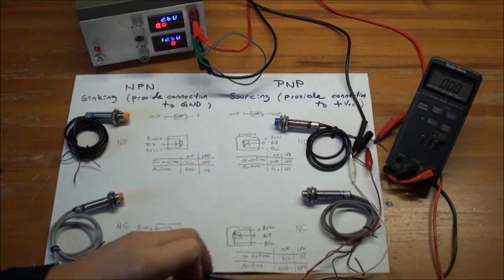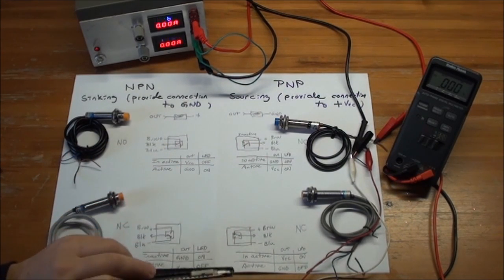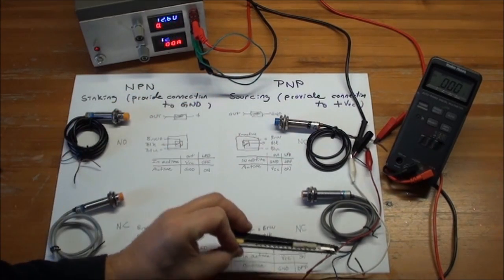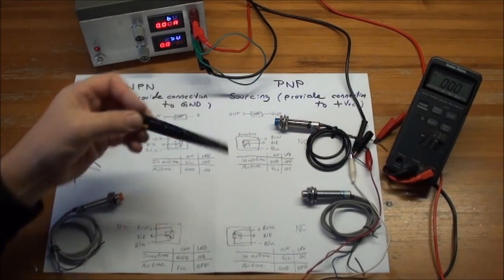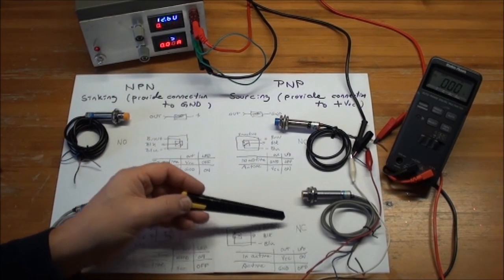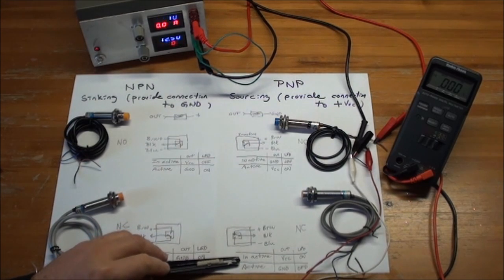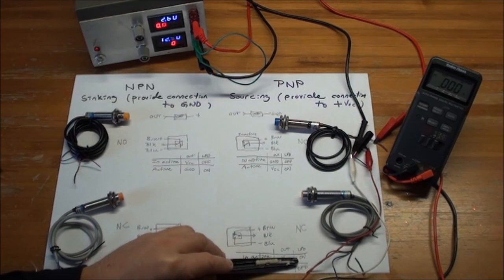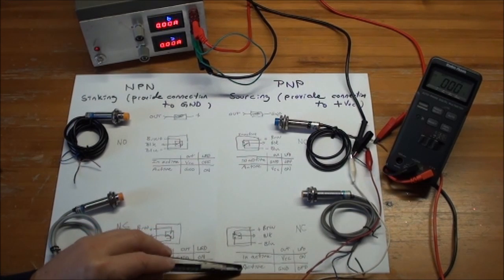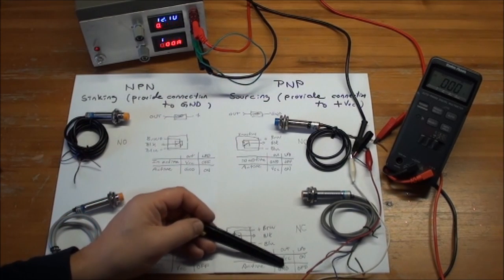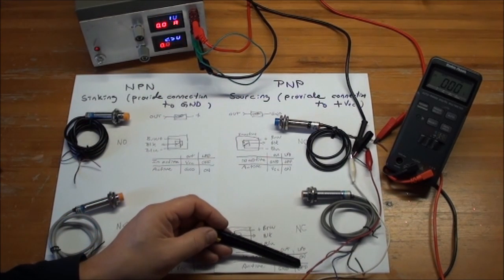And then of course the last one, I think we can skip connecting that one, is again a mirror image of this one and this one. So in the PNP normally closed situation, what you would see in the inactive state, if I connected it, is that you got 24 volts out and the LED would be on. And in the active state, when you activate it, you will get ground out and the LED will go off.